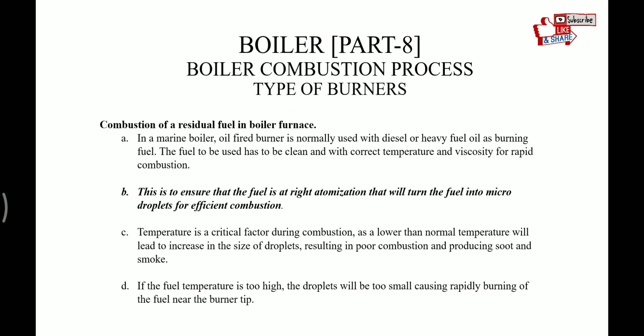Combustion of residual fuel in boiler furnace. In a marine boiler, an oil-fired burner is normally used with diesel or heavy fuel oil as the burning fuel. The fuel to be used has to be clean and at the correct temperature and viscosity for rapid combustion. This is to ensure that the fuel is at the right atomization, which will turn the fuel into micro droplets for efficient combustion.